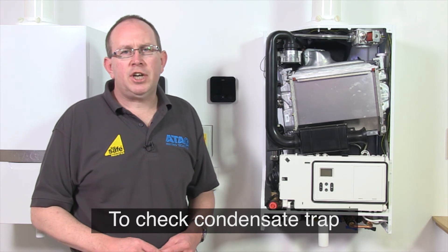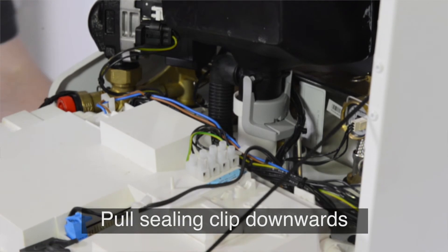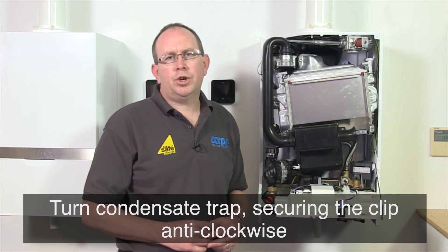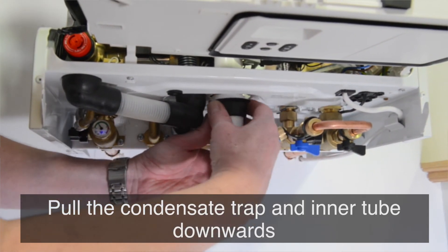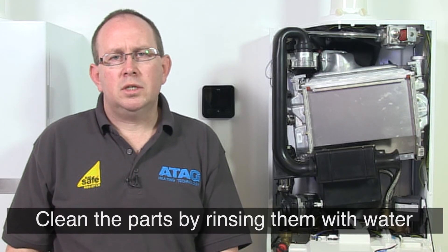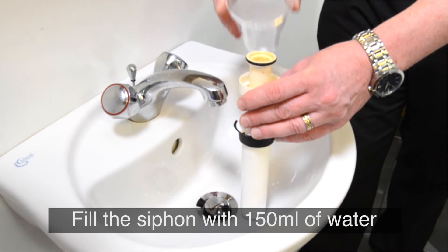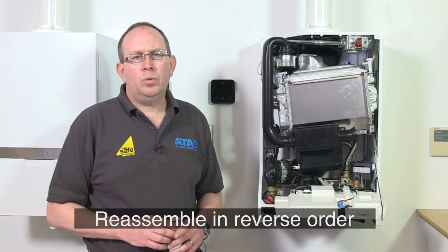The condensate trap also needs to be checked. To do this, firstly release the control unit forwards. Turn and pull the sealing clip downwards. Turn the condensate trap securing clip anti-clockwise. Next, pull the condensate trap and the inner tube downwards and clean the parts by rinsing them in water. Then refill the siphon with 150 millilitres of water. Finally, reassemble in reverse order.